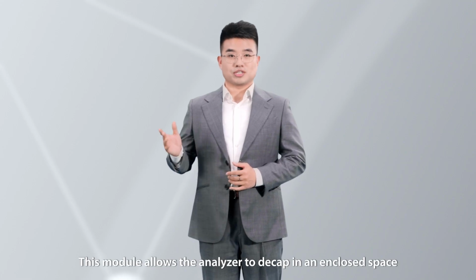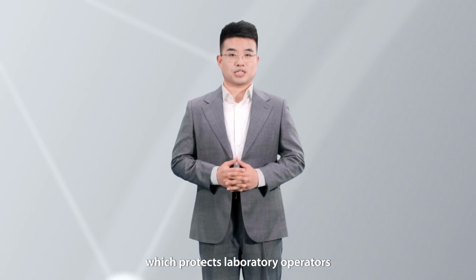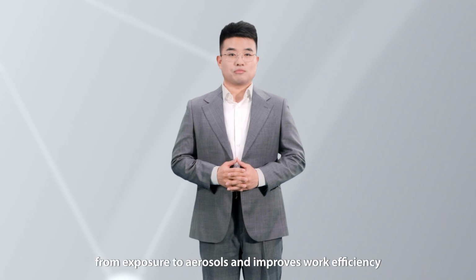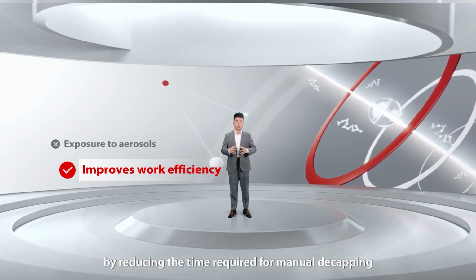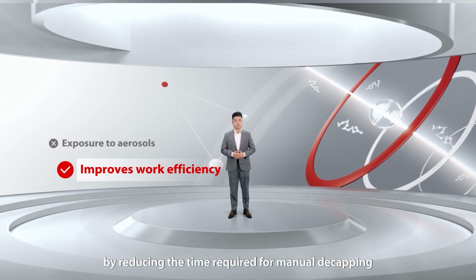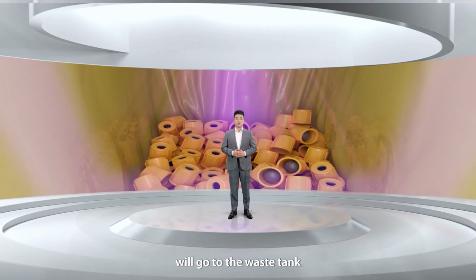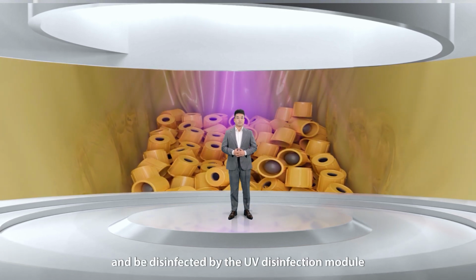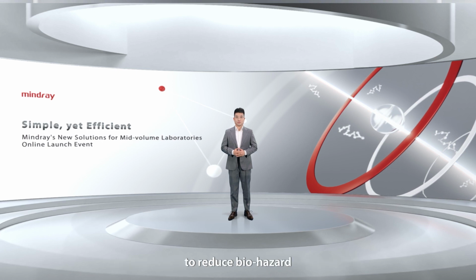This module allows the analyzer to decap in an enclosed space, which protects the laboratory operators from exposure to aerosols and improves efficiency by reducing the time required for manual decapping.